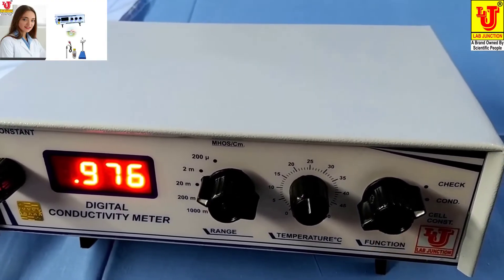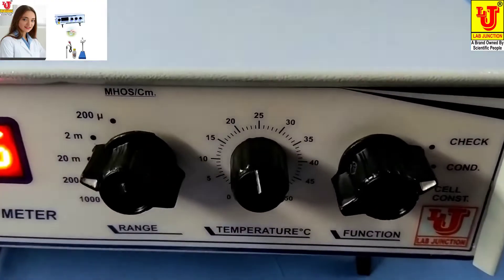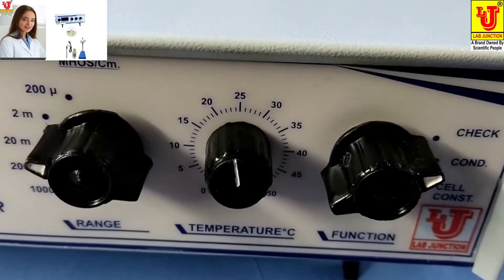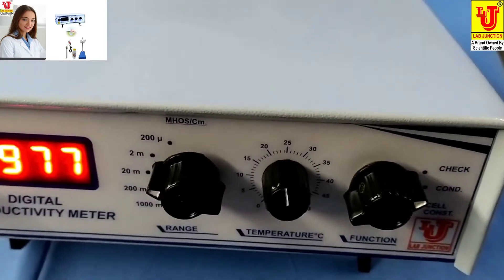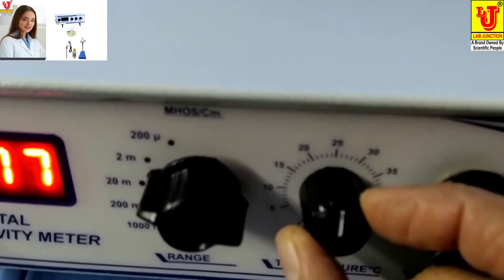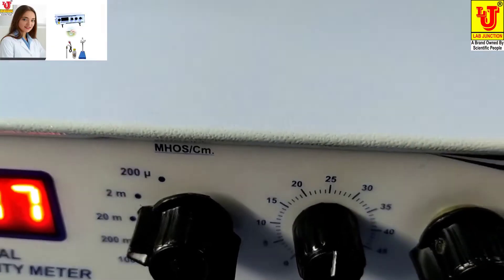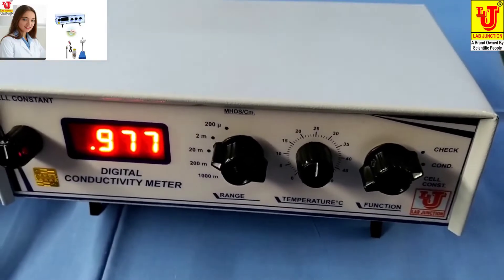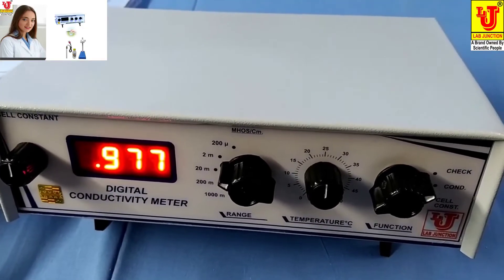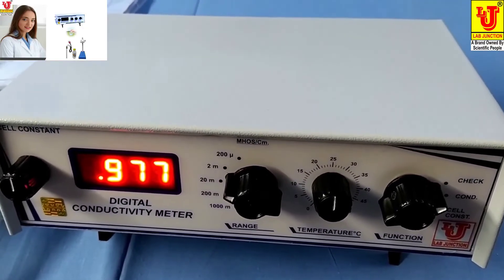In the function control, three positions are there: check, conductivity, cell constant. Now, first of all, you have to set temperature 25 degrees. If you have your own temperature, then you can set to your own temperature as you have desired your conductivity on that temperature.